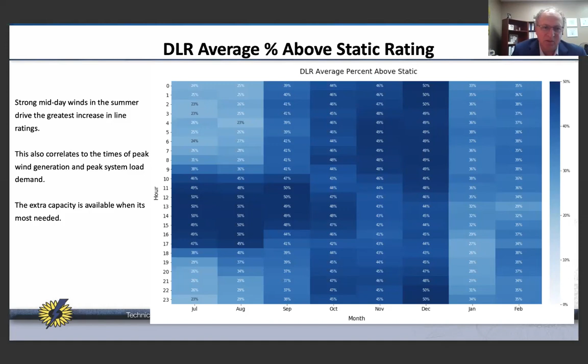Since we are upgrading the line and it should be in service here in the next month or so, we looked at the same data and we say, if we move the line rating up to 3000 amps, which will be the static rating that we will use normally, and if we projected those DLR data onto that line, you could see the difference here, the percent of time that the DLR is actually giving us a higher rating. Also, what the DLR showed us is there are a few hours in that time span where we see the static rating is too high. There is like 3% of the time where, based on wind speed and ambient temperature, the rating is too high and should be a little bit lower. So this is a great thing to look at, because you could increase the rating most of the time. However, if you implement the DLR, you could have visibility over when am I above the static that I assume, when am I below it. Next slide.